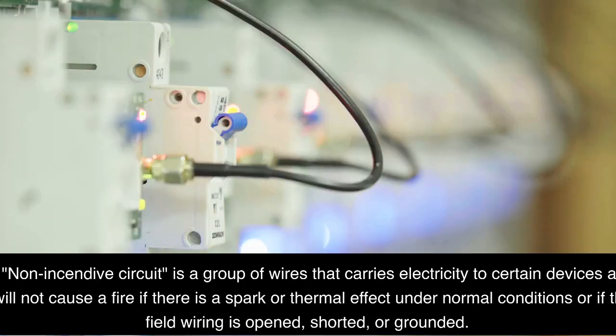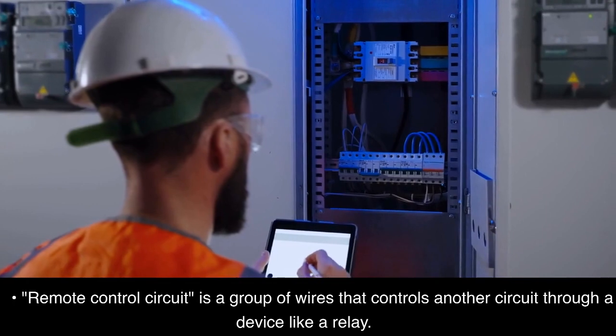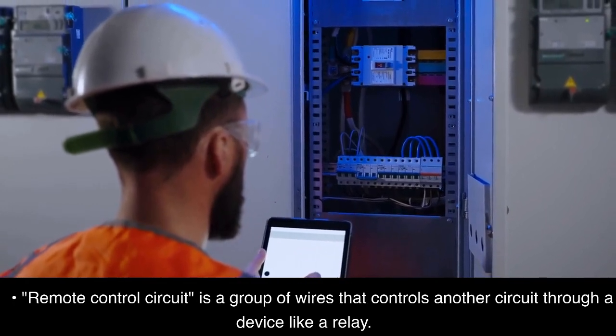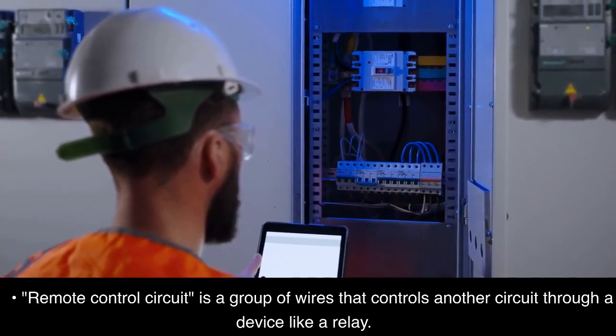Non-incendive circuit is a group of wires that carries electricity to certain devices and will not cause a fire if there is a spark or thermal effect under normal conditions, or if the field wiring is opened, shorted, or grounded. Remote control circuit is a group of wires that controls another circuit through a device like a relay.